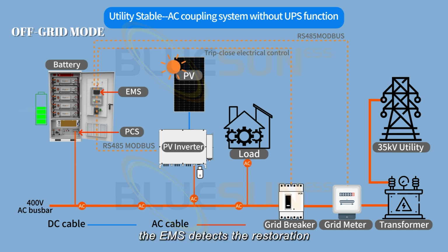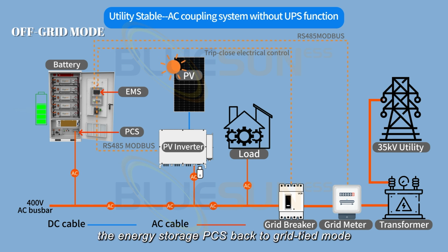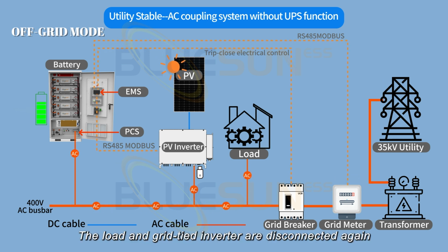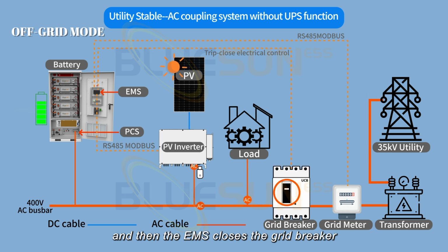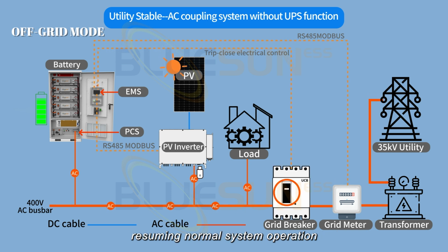When the mains power returns, the EMS detects the restoration of mains power and first switches the energy storage PCS back to grid-tied mode. The load and grid-tied inverter are disconnected again, and then the EMS closes the grid breaker, resuming normal system operation.